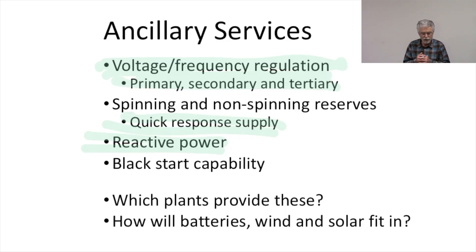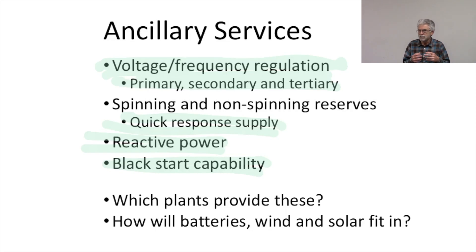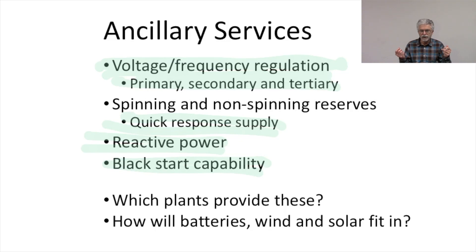Another key characteristic of power plants is black start capability — can this power plant start up if there is no electricity out there? Many plants require the grid to be active and providing electricity in order to start back up, and yet we need a certain configuration of assets that are able to start up in the absence of power.